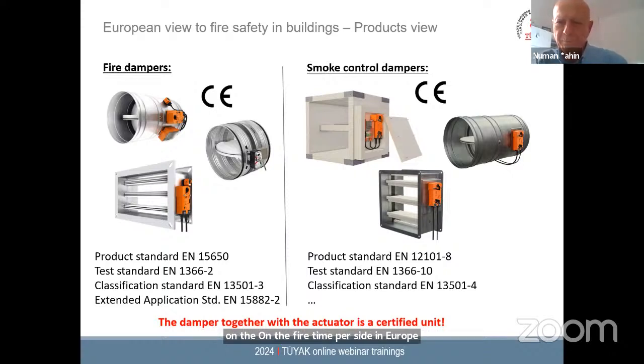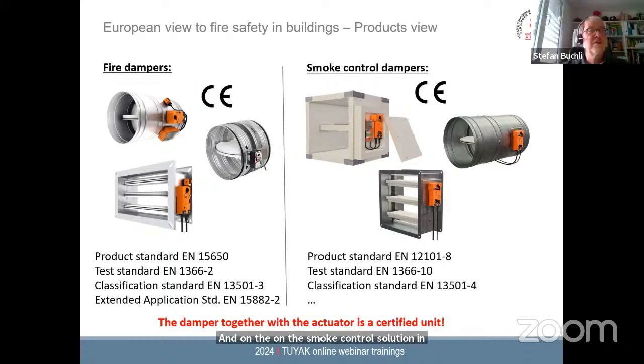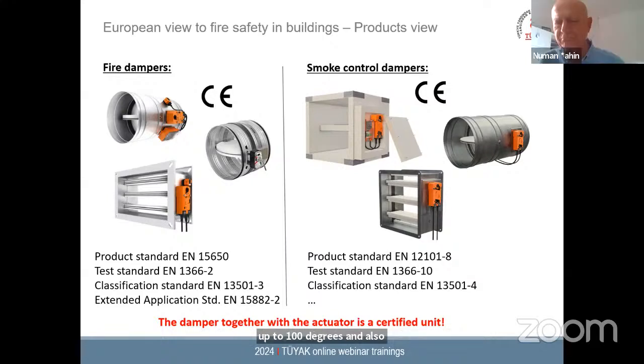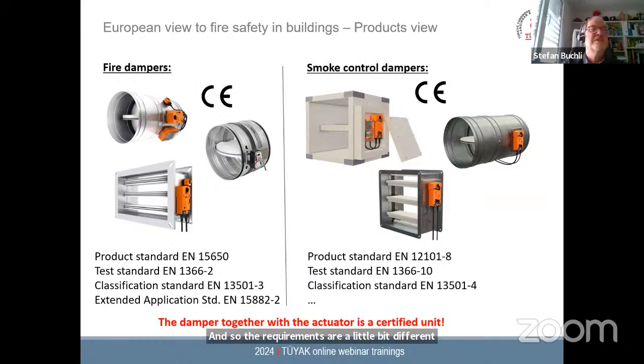Mhm. And on the smoke control solution in Europe, we have also a little bit of a different situation. There are some applications in which the fire brigade must also be able to control the dampers in a fully developed fire, and there we use a thermo protection housing. But even in the housing you have temperatures going up to 100 degrees, and the actuators also have to operate there. So the requirements are a little bit different, and therefore the design is different.